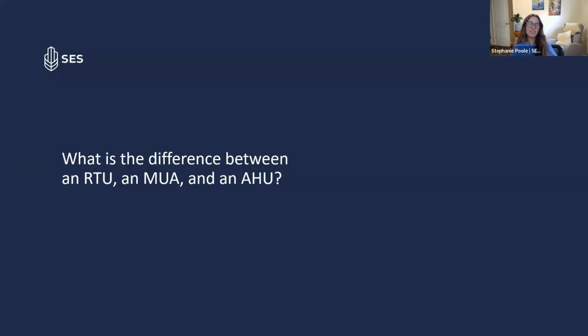Thanks. Really quickly, because this is not well understood, I just want to highlight the difference between an RTU, an MUA, and an air handling unit, because what we're talking about here is mostly RTUs, but I will touch on MUAs. So an RTU, rooftop unit, is what you'll typically see on a roof. Now, to be fair, they could also be on the ground. It could be a packaged rooftop unit, but the difference with a rooftop unit is that it's mixed air, which means it takes return air from the space and outdoor air from outside, mixes it together, heats it and cools it, and sends it into the space.